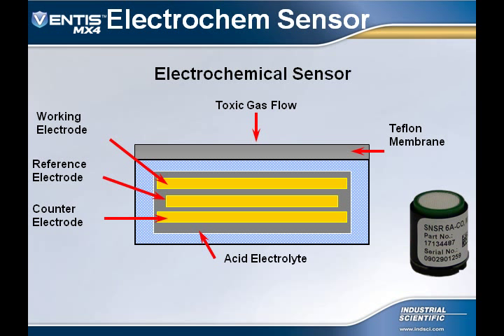This screen shows the same thing you saw earlier. You have your 3 electrodes and the acid electrolyte. Some say it's just like a battery. Now the difference between a battery and an electrochemical sensor is that the battery is always producing current, and the electrochemical sensor is only producing a current when the gas that it is designed for enters the sensor.